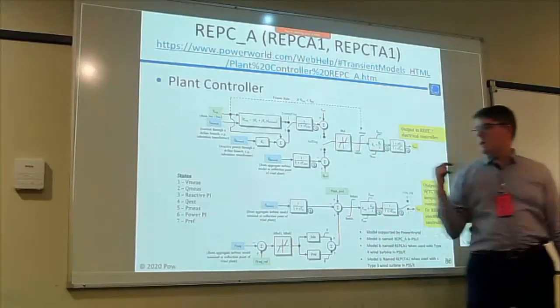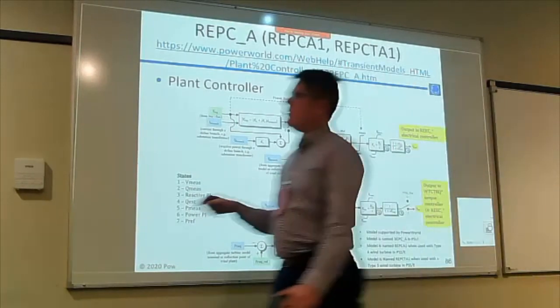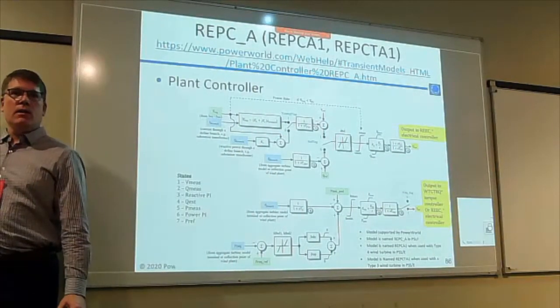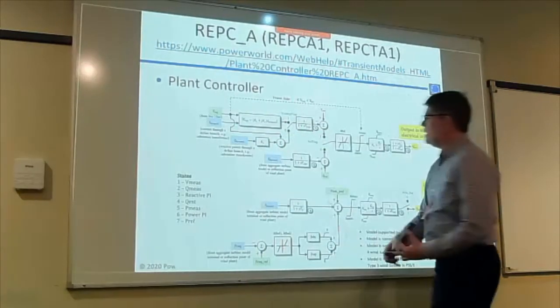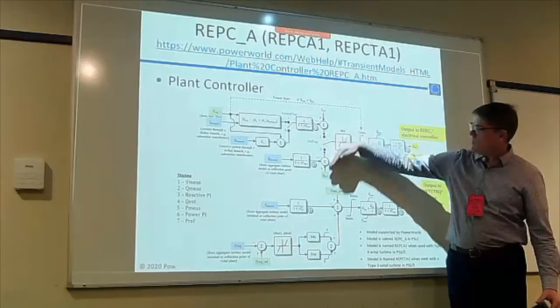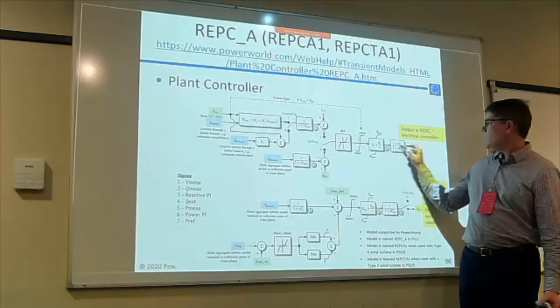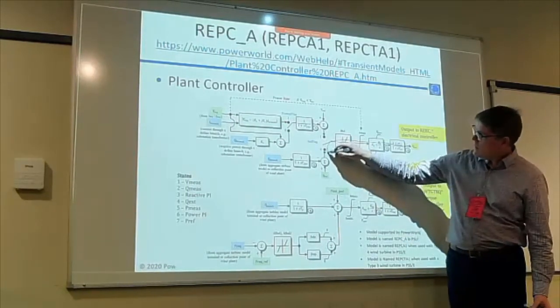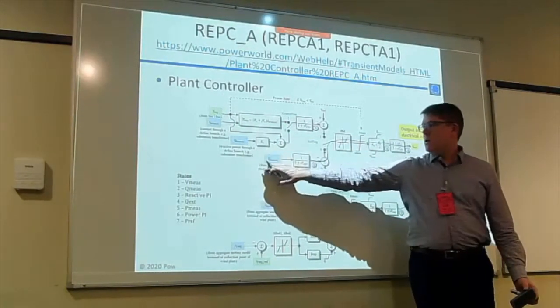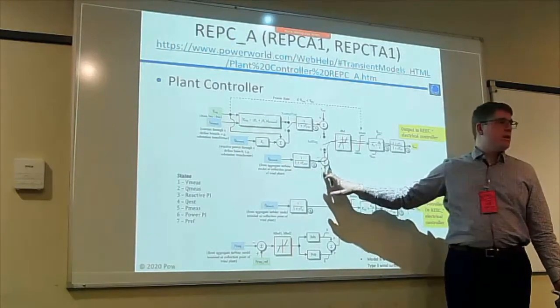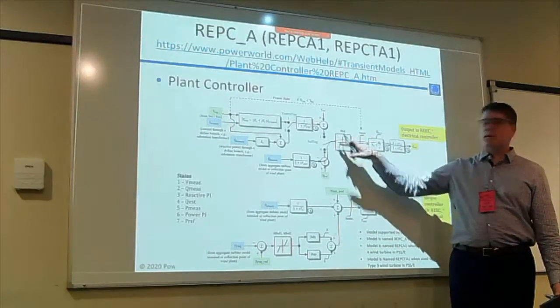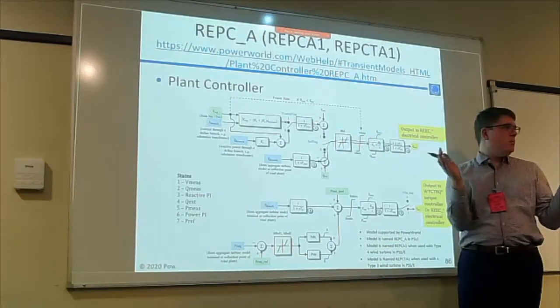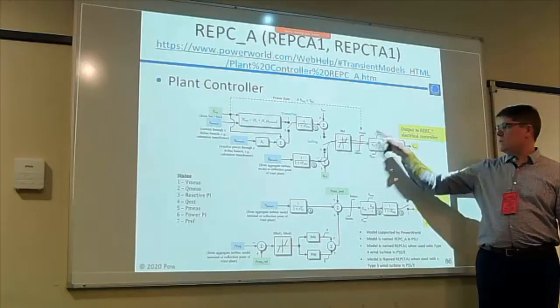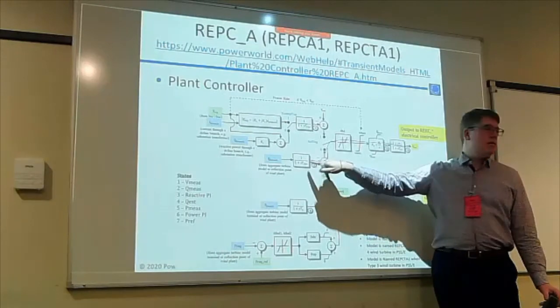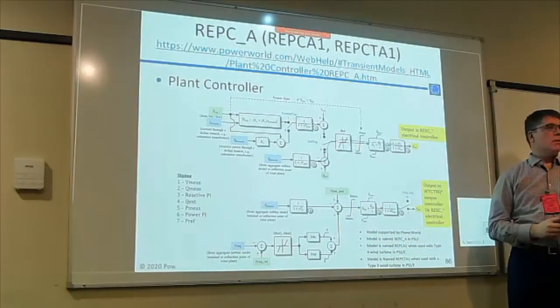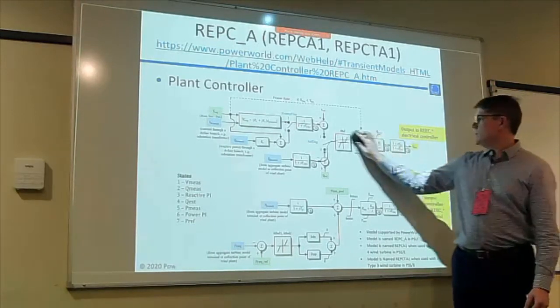If I wanted to regulate to constant, or try to keep the reactive power out here constant, I would come in here and set this ref flag to 0 to send the signal down this way. So I'm coming in here, going this way, and measuring the reactive power on that branch, comparing it to where it starts, and running it through a deadband—so if I move just a little, maybe I don't respond. There's an error min-max, run it through a PI loop, and it's going to drive this value to 0, trying to bring it back to where it started. So that'd be for constant Q.